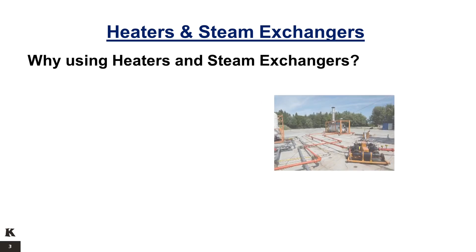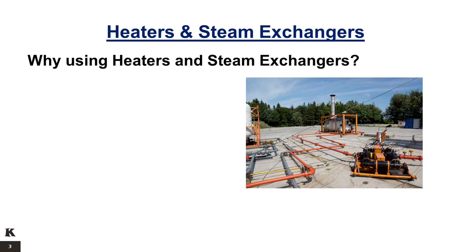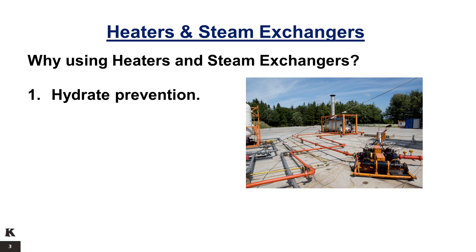Heaters and steam exchangers are used to raise the temperature of well effluent for a number of reasons. 1. Hydrate prevention. Water is often produced from a well in varying quantities and is often unavoidable. Natural gases also contain a proportion of water vapor. Under certain choked flow conditions, the change of conditions across a choke is sufficient to lower the temperature such that free water and light hydrocarbons in the natural gas become solid. Natural gas hydrates have the appearance of hard snow and are formed above the normal freezing point of water. Certain gases, particularly H2S and CO2, promote the problem. Hydrates can become a serious problem by causing valves and flow meters to become inoperative and chokes to plug. A heater may alleviate this problem.